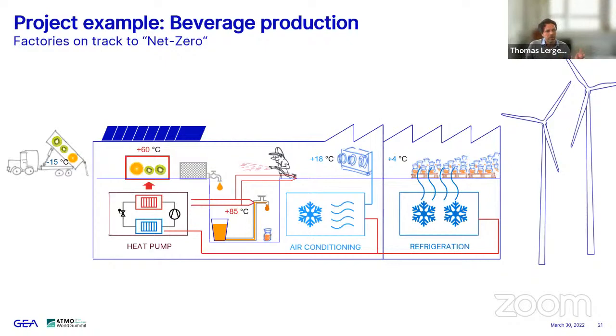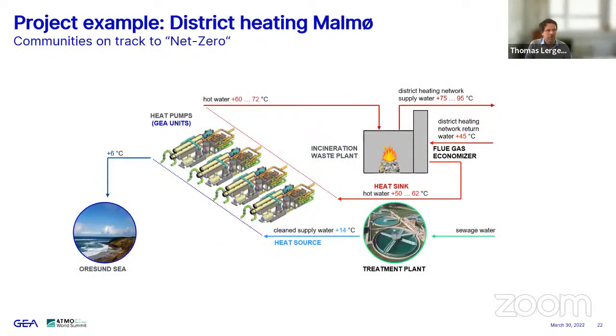The second big application aspect of heat pumps is not process heat, but district heating. And here's a project example from Sweden in the city of Malmö. So this is now communities on their track to net zero. Sorry, this slide is not animated. You see everything at once now, but let me take you through this. At the heat source, they're able to take the sewage water, some wastewater. They're cleaning this very, very clean, and it's available at plus 14 degrees Celsius, approximately. And then this heat source is injected into 4 very large GEA heat pump units, and it's cooled down to plus 6 degrees Celsius. And because it's treated, they can put it directly in the Öresund Sea.